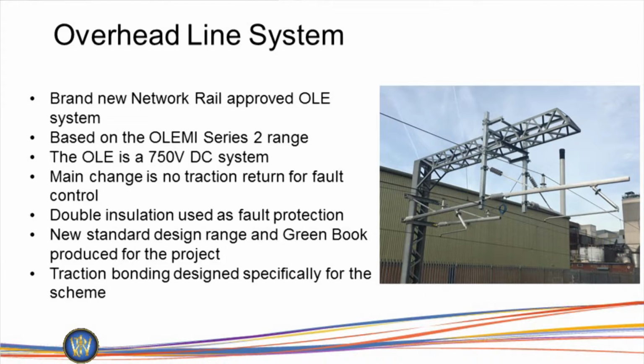Obviously the problem we've got is with the DC system, there's no traction return, whereas with the AC standard Network Rail there is. So we've got the issue of double insulation - all tramway systems are double insulated, so if one insulator fails, your second insulator is your backup. Obviously with this, there was no backup system, no second insulator.